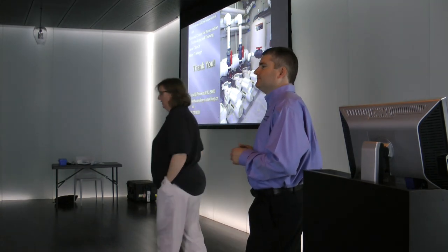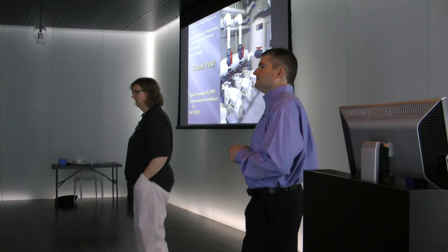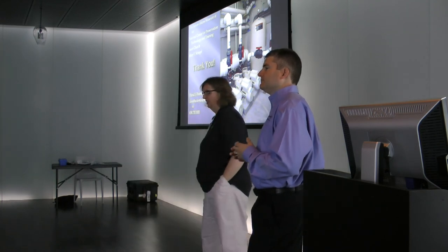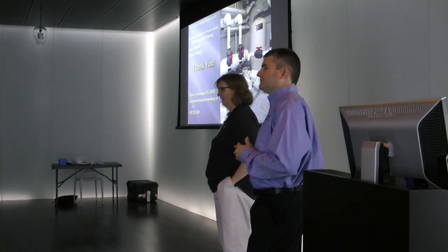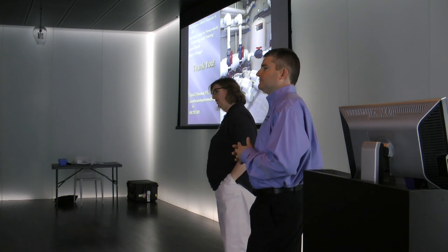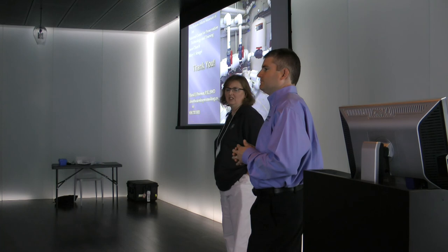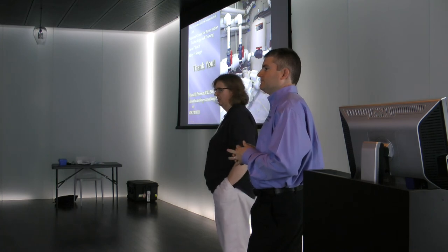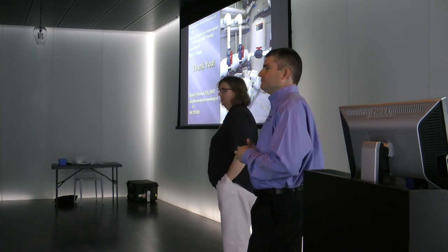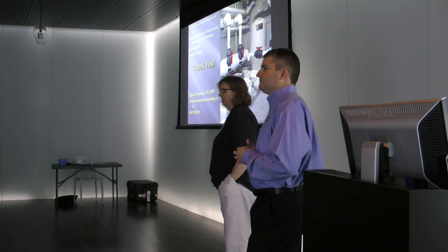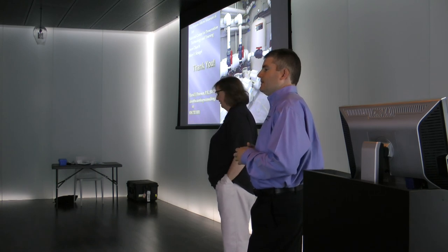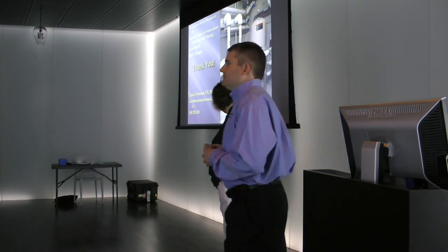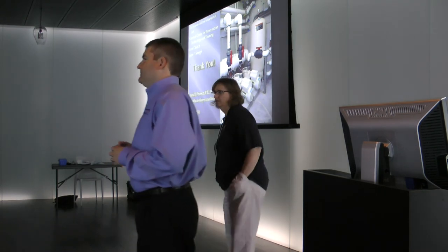I thought there had been a question, or yeah, I have Tom? A quick question. You know, on the variable drive pumps, so you can adjust the speed of the motor to put out a certain amount of water. And pumps have to run in what they call the sweet spot, so that there's some back pressure against the impeller to make everything run right. So do you still have a valve on the outflow that you can adjust to put enough back pressure against the pump? So I'm just curious how...